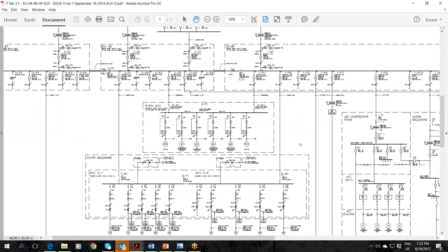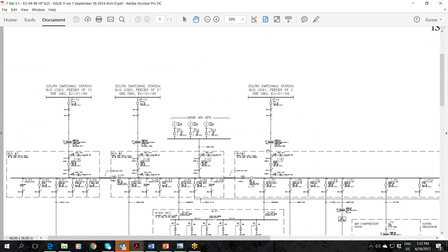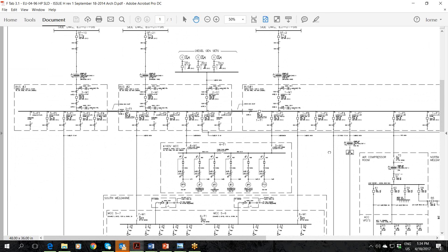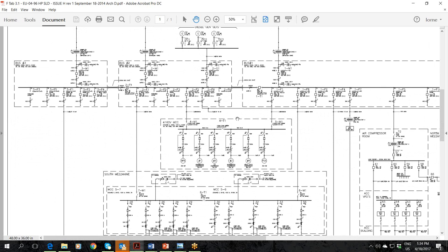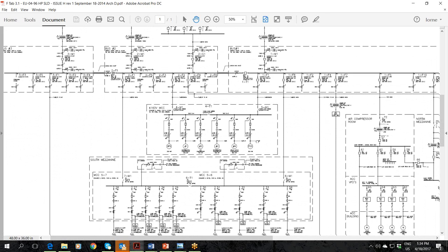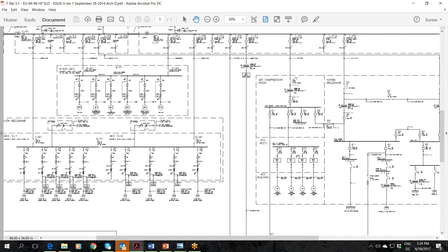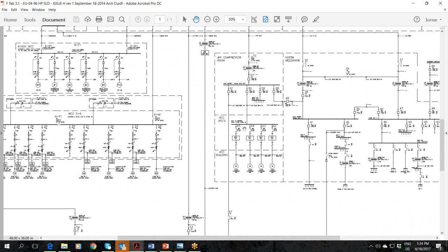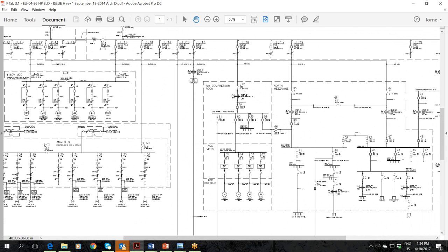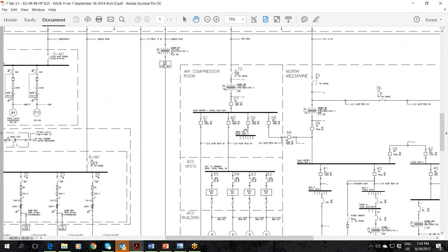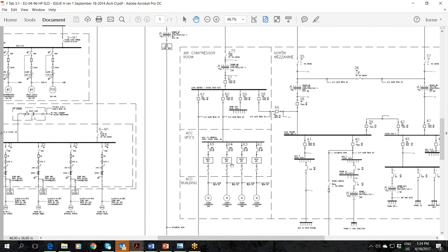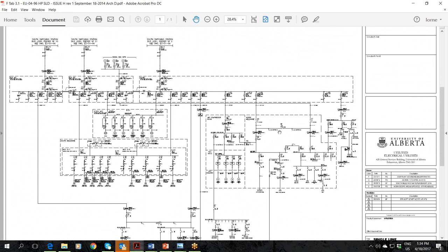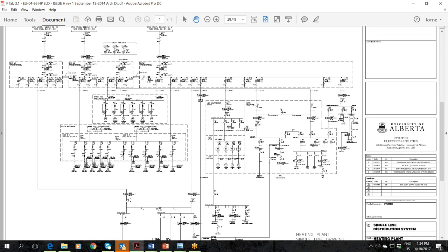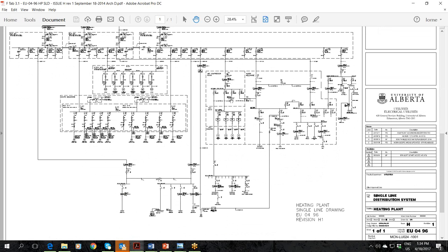So again, 3 buses only operating right now on 1 supply. This is step down. These are the transformers that we saw outside that step down from 13.8 kV to 4160 volts. So everything in the heating plant is 4160, which is why you don't see another transformer here for the larger motors, 4160 volt motor control centers. You do have step down to 120/208 for plugs and lights and smaller things. Actually, this is 600 volt. My apologies. This goes to some VFDs that then run our air-cooled condenser associated with steam turbine generator number 2.